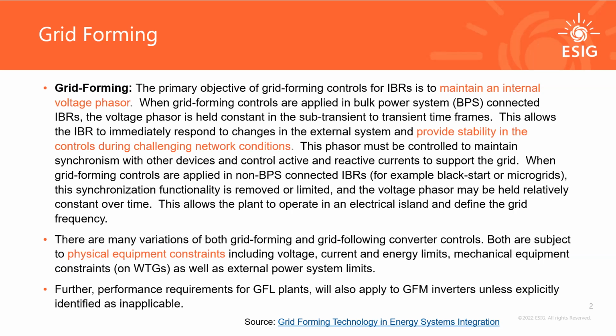According to that definition, the primary objective of grid forming controls is to maintain internal voltage phasor. When grid forming controls are applied in bulk power system connected inverter-based resources, the voltage phasor is held constant in subtransient and transient timeframes. This allows the inverter-based resource to immediately respond to changes in the external system and provide stability in the controls during challenging network conditions.